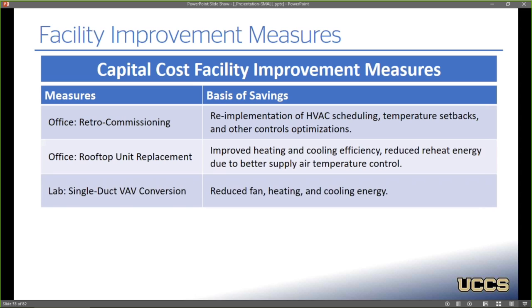At the lab building, they also want to look at replacing that equipment. They've had numerous issues with it, and we agree with that. And while we're replacing that equipment, we would recommend they go to a single duct VAV type system, because they're not really using it much as a lab, and even if they do turn those fume hoods on, there's no reason this converted system wouldn't be able to return to that original design condition.